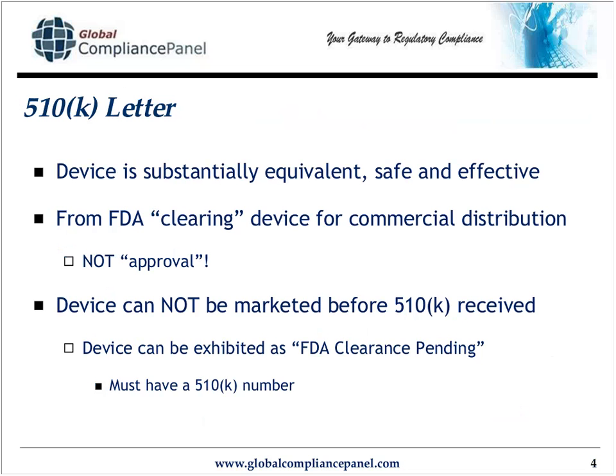I like to begin at the end, which is to say the 510K letter, not litter, sometimes maybe, is the document that you receive from the agency stating that your device is substantially equivalent to an existing device called the predicate device, that your device is also safe and effective based on data that you provided in your submission. This letter from FDA clears your device for commercial distribution. It does not approve your device in any way for any use at all.